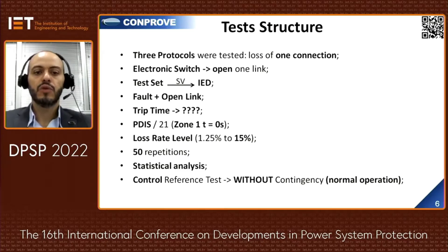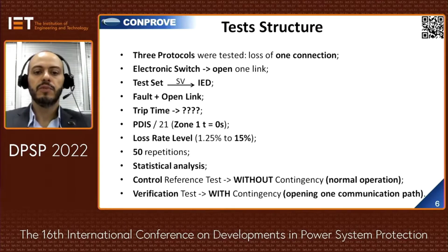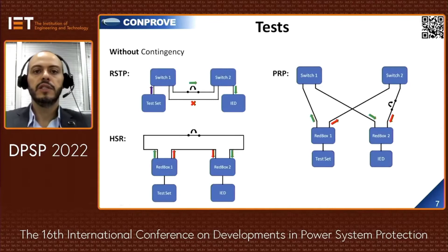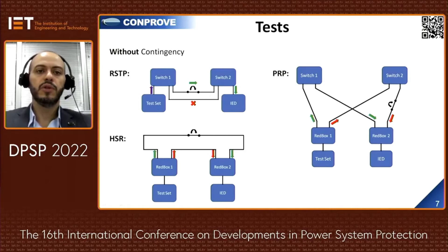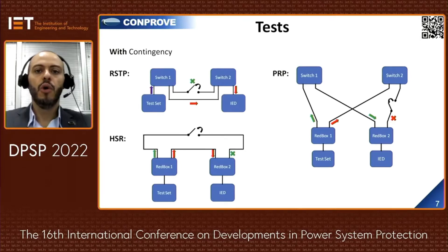The control reference test was performed under normal operation, meaning without contingencies. The verification test was performed by opening one communication path, meaning with contingencies. This slide illustrates the test structure with the switch, test set, red box, and IEDs — first without contingencies considering the three protocols RSTP, PRP and HSR, and then with contingencies opening the paths.